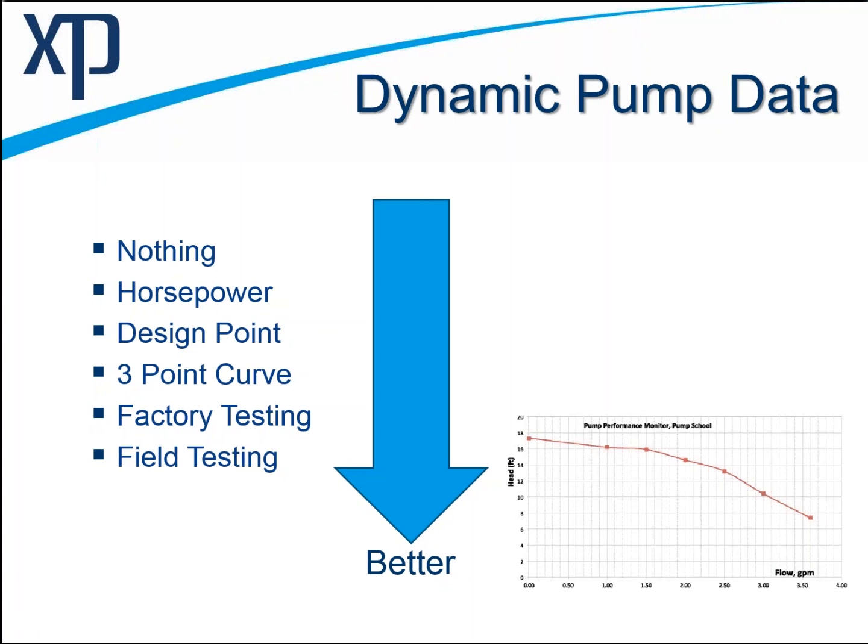On the other end of the spectrum is if you don't have any head, the pump just runs out and basically can't produce much of anything. It's trying to add flow, but there's no head to it, which is kind of sitting there spinning and nothing's happening. Both of those are not ideal. I can tell you, no matter what your pump looks like, it's not made to be efficient at either end of those spectrums, so it's not ideal to have a pump running that way.